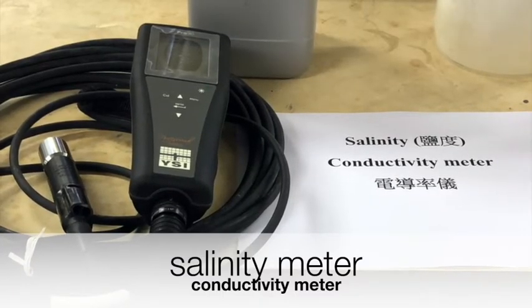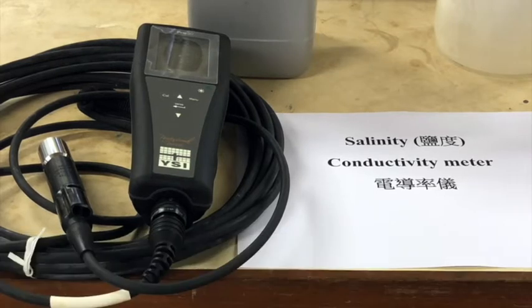This is a salinity meter or conductivity meter which is used for measuring the salinity of the water sample. There's a huge difference between the seawater and freshwater. The seawater sample contains lots of sodium chloride. For the freshwater, the salinity should be 0. During the dissolved oxygen measurement, the parameter of salinity has to be entered into the instrument, so we have to measure the salinity before measuring the dissolved oxygen.